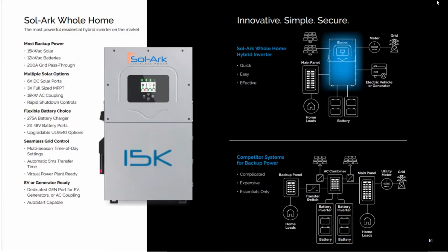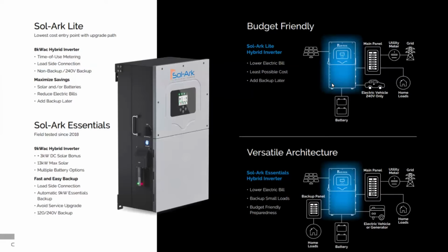all at the same time so elegantly. You might have to identify a way to throttle that back, such as using the generator's native controls to only run the generator during non-solar hours if you want to have it all. If you want to have microinverters and use the gen port for something else, put the generator on its own transfer switch. So when you want to design with generators, I would strongly say that is a reason to either use the gen port on the Sol-Ark or to go with DC coupling rather than microinverters.